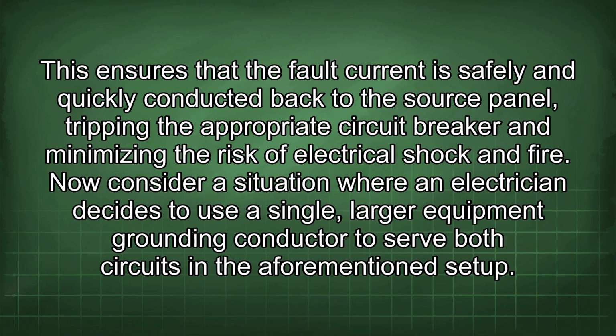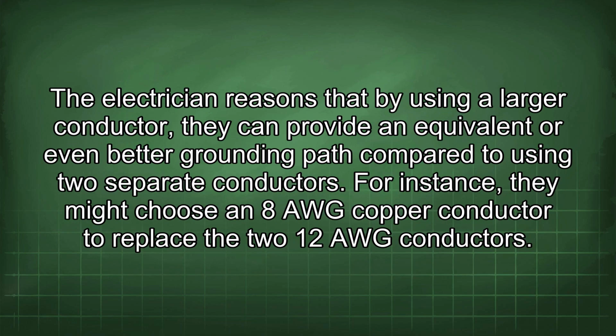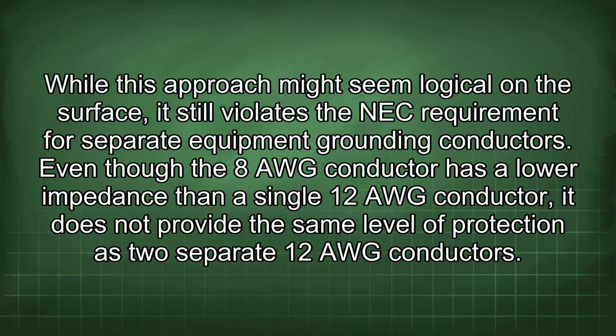Now consider a situation where an electrician decides to use a single, larger equipment grounding conductor to serve both circuits in the aforementioned setup. The electrician reasons that by using a larger conductor, they can provide an equivalent or even better grounding path compared to using two separate conductors. For instance, they might choose an 8 AWG copper conductor to replace the two 12 AWG conductors. While this approach might seem logical on the surface, it still violates the NEC requirement for separate equipment grounding conductors.